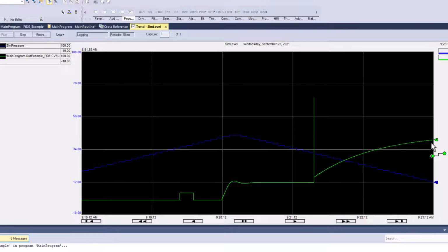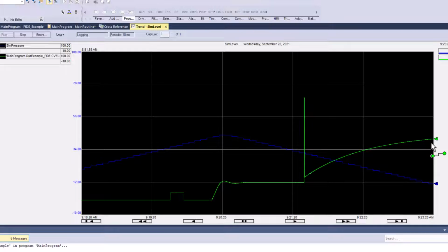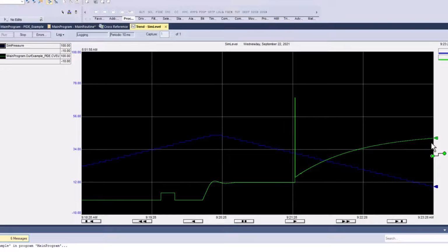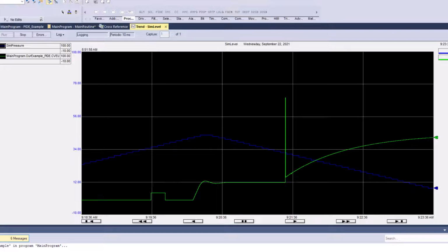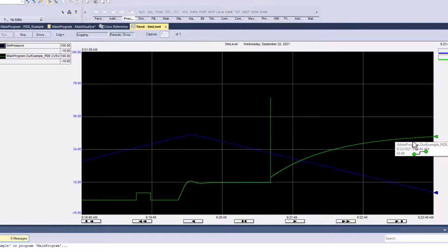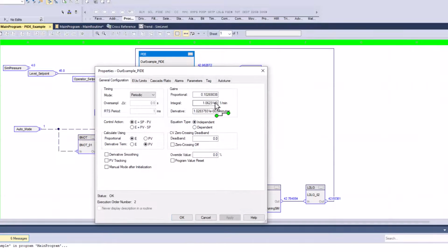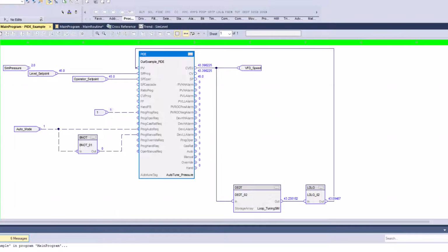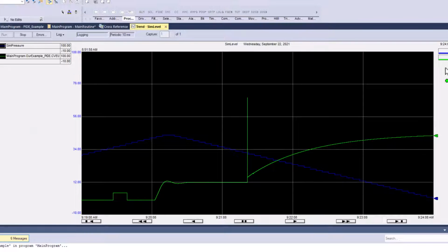But again, that all depends on how your PIDE process loop looks, right? All the physical devices you use, all the timing, the latency of timing, I should say, and the way it's set up inside of your actual ControlLogix, with this, in my case, being 100 milliseconds for the scanning rate of the PIDE loop. So we're getting pretty close to our set point. You can see it's still traveling. It's not quite as aggressive, but you can see it's traveling. What it's doing, if I can explain this, is it has very little proportional, so it's using a lot more movement from the integral, and then it has derivative to put the brakes on things a little bit. So let's see that. We're getting right at the point where we should be.